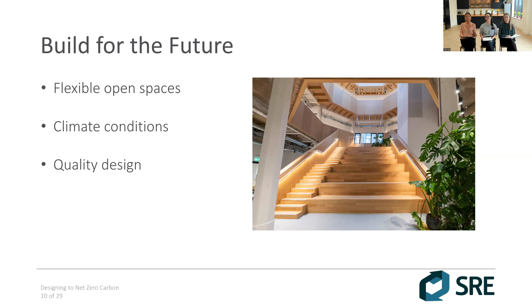Before going into the details of designing out operational carbon, we need to consider the highest energy loads for different developments. Offices tend to have high lighting, heating, and cooling loads, whereas warehouses, with large unconditioned spaces and no heating or cooling, predominantly have high lighting energy consumption. Industrial units may have bespoke machinery and equipment, leading to high unregulated energy loads, and residential units, including student accommodation, hotels, and care homes, generally have high heating and domestic hot water demands.